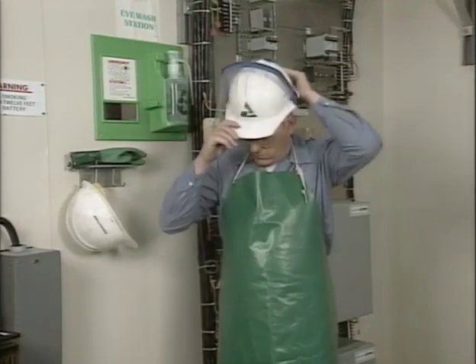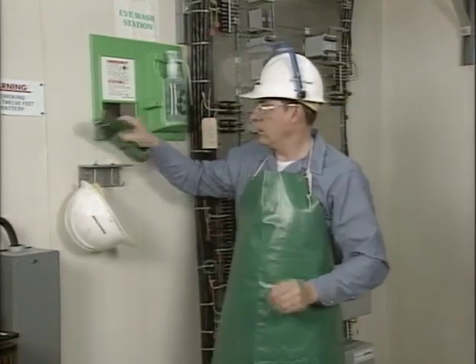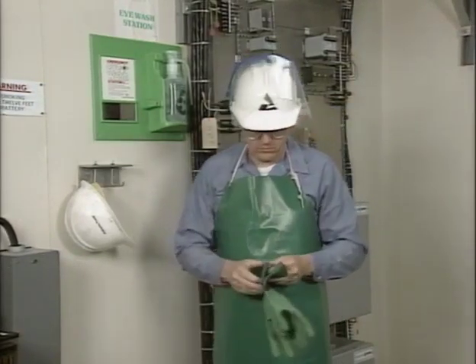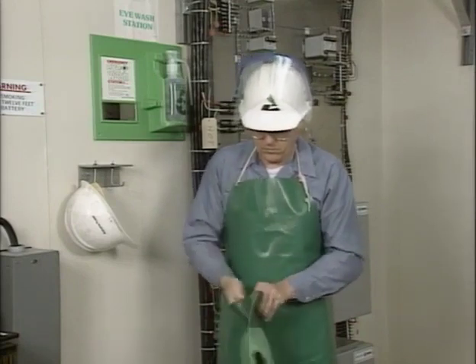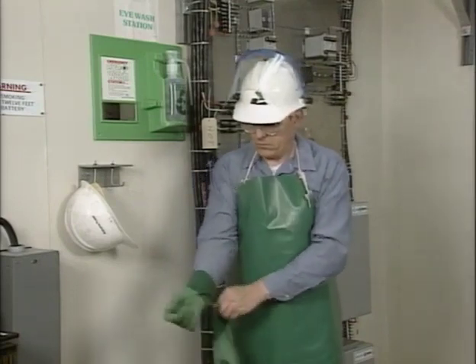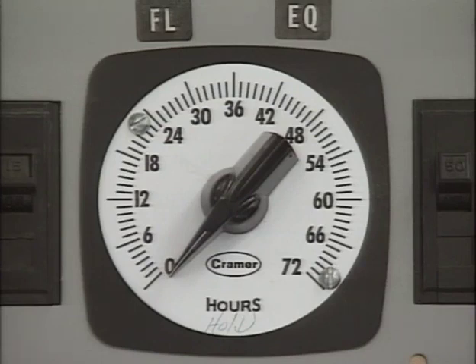As with any other work done on a battery, all the required safety equipment should be worn and all safe working practices should be followed during the impedance testing. In addition, the battery charger should be in the float mode and should be supplying current to the DC loads. The battery should not be discharging.